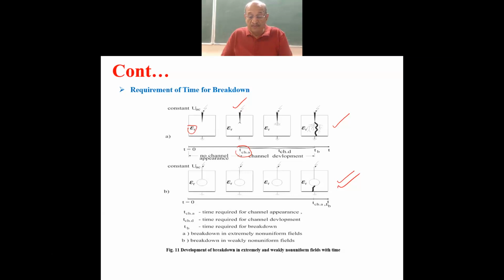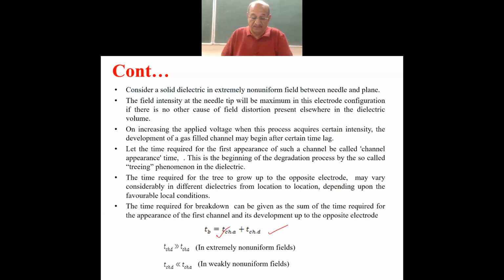So, the partial breakdown activity had given rise to treeing phenomenon, and extension of the treeing phenomenon led to breakdown in extremely non-uniform field. And unlike there, in weakly non-uniform field, no PD and the breakdown takes place directly. As you can see in this schematic.